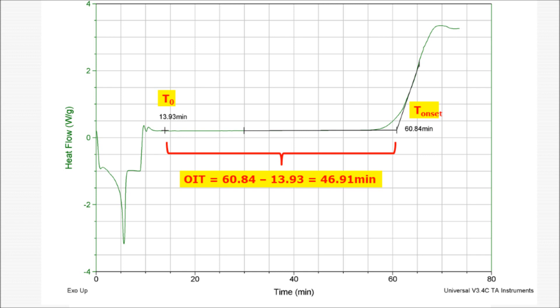After this, calculating the OIT for this membrane is extremely straightforward. Simply subtract T sub 0 from T sub onset, and the result is the value for this material's oxidative induction time. These calculations are identical for both the standard and high pressure OIT.